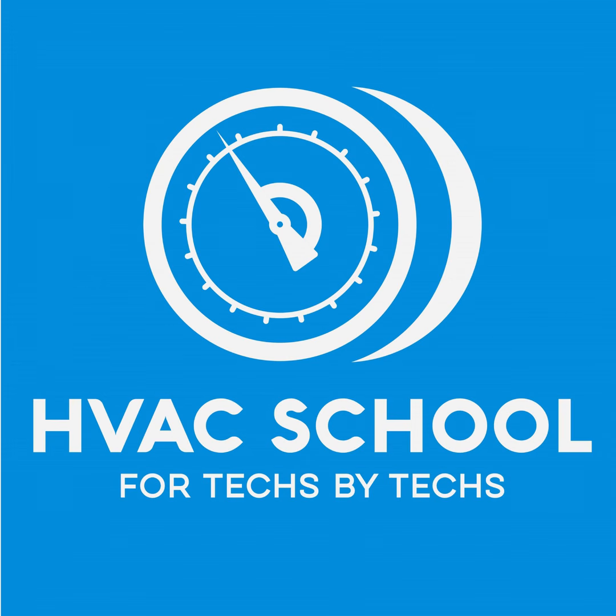As we're heating and cooling simultaneously on these systems, we get some really nice efficiency benefits. AHRI had to basically come up with a new efficiency term or standard, SCHE, which is simultaneous cooling and heating efficiency, which applies to all manufacturers that have some sort of heat recovery equipment. Because of the efficiency, you have your interior spaces that need cooling regardless of the outside temperature. So we're sending liquid refrigerant to the indoor units. It's evaporating off, pulling the heat out of the space, and we're going back to that branch box. Instead of just going out to an outdoor unit and rejecting that heat, there's some heat recovery, hence the term. There's some of that going on in a system like that.